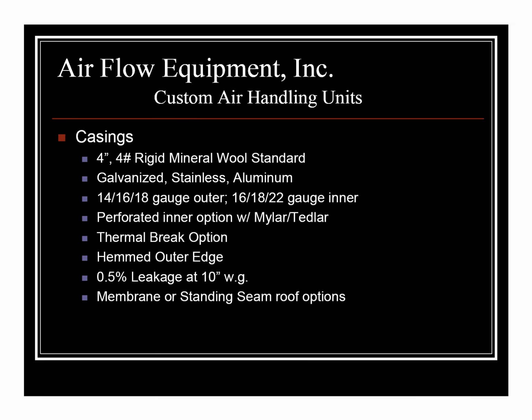A couple other things to point out. Thermal break is definitely an option, and maybe you're asking yourself, why is it an option? Well, what we found through the years is using the 4-inch casings with 4 inches of mineral wool, if you have standard discharge temperatures that are 54, 55 degrees, really at that point a thermal break is not even needed to avoid condensation. When you start getting down into the real low discharges, 52, 51, 50, then a thermal break is definitely a good idea, and we will build a no-through metal panel base so you can get that true thermal break option.